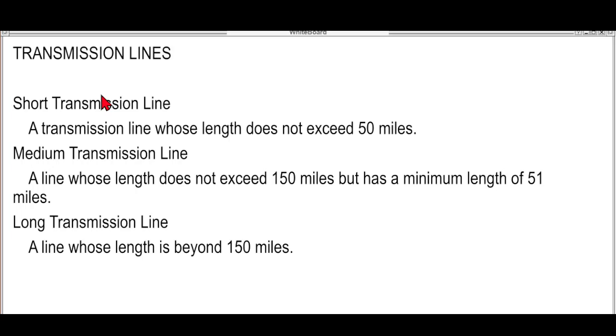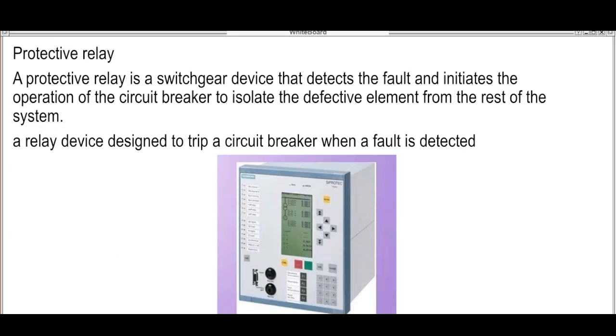A short transmission line is a transmission line that does not exceed 50 miles. A medium one is a line that does not exceed 150 miles and has a minimum length of 51, so 51 to 150 miles is a medium transmission line. Once it exceeds 150 miles, that is what we call a long transmission line.